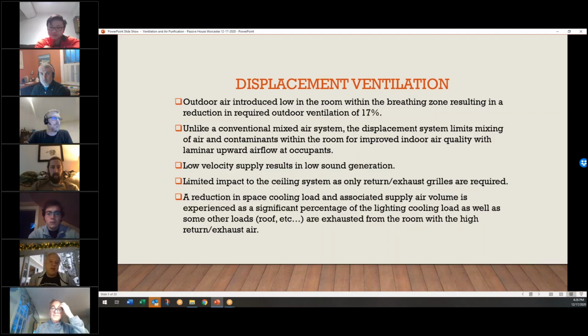Reduce your space cooling load. And also you can use economizers. I mean, most displacement air, the coolest your air would come in would be like 63 to 65 degrees. So anytime the outside air is below that, as long as it's dry enough, you can use it as economizer, as opposed to a mixed air system that you might need at 55 or 58 or colder. So there's a lot of benefits to it.